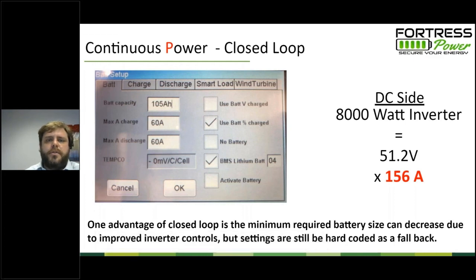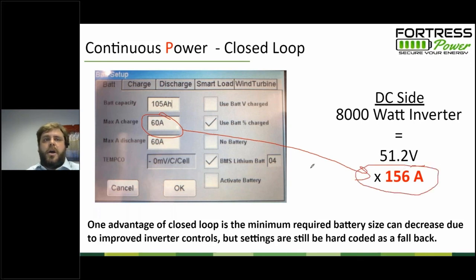One advantage of closed loop communication is that normally, in our example, if you take a 60 amp hour battery and the inverter is capable of drawing 156 amps out of it, then you would need 3 of these batteries to stay within the spec of the battery inverter. But in our first introduction class, we mentioned that lithium ion batteries are capable of a faster rate of charge and a faster rate of discharge.